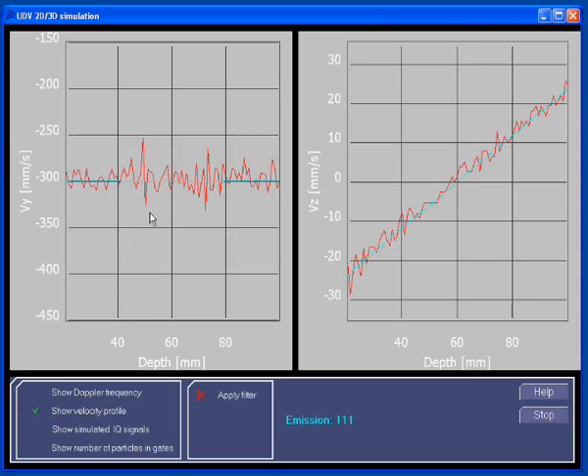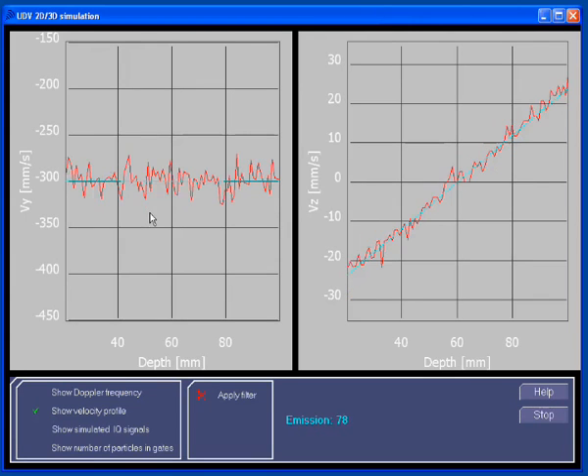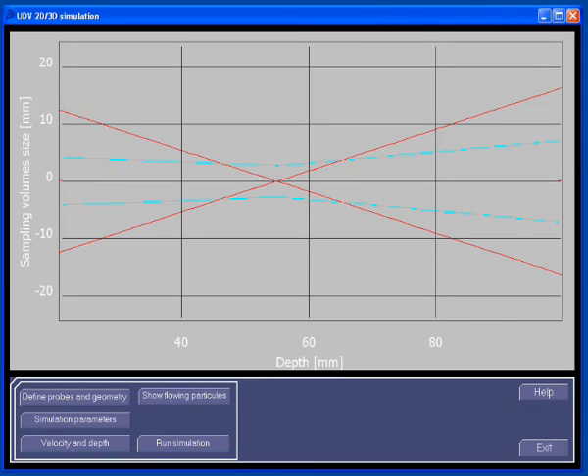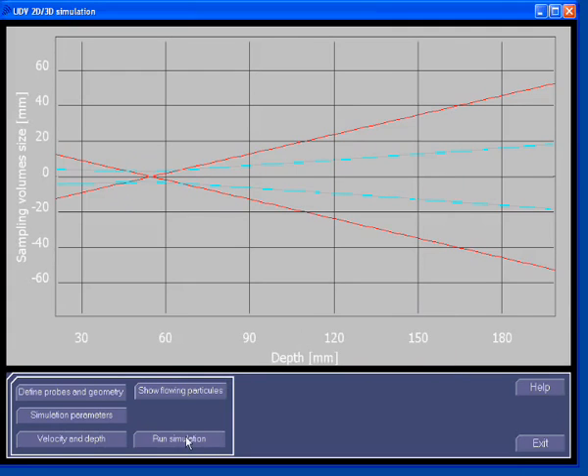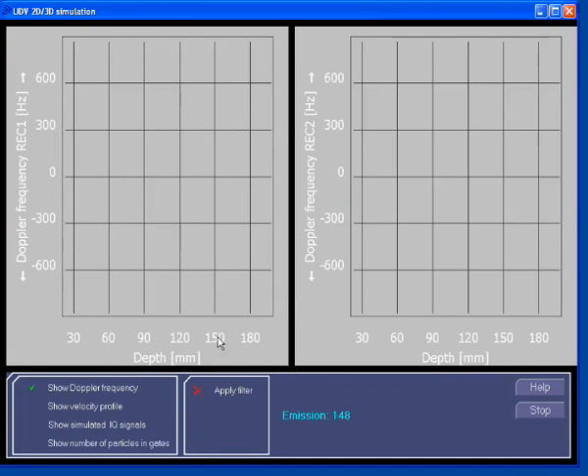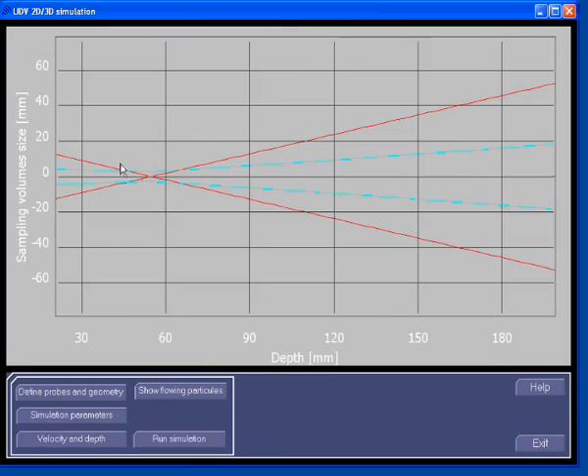Let's see the influence of an increase in the measuring range. Let's go into the velocity and depth range panel and change the maximum depth to 200 mm. You will notice that the maximum velocity changed also a little bit. Looking at the result of the simulation, the velocities are not correctly measured at higher depths. The real reason comes from the position of the probe — the beam crosses at a distance too close from the origin, so we have to move that point. Also, the beam width is too big at higher depths.